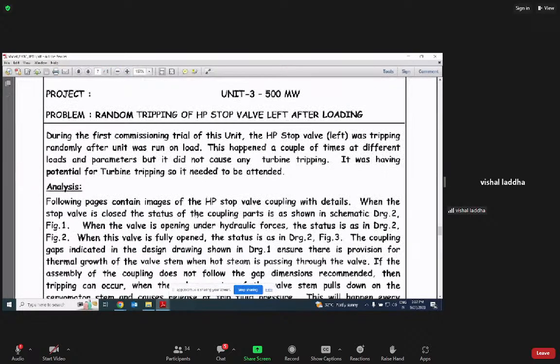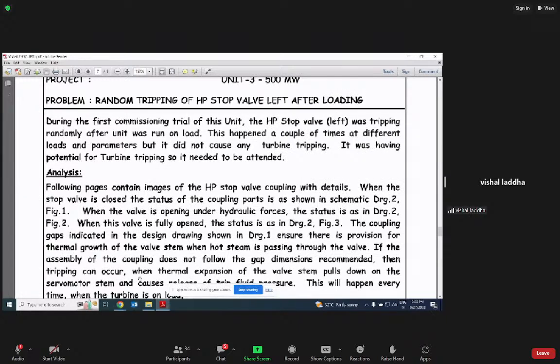Next is case number 2: random tripping of the HP stop valve left after loading. This is a 500 megawatt case study. During the first commissioning trial of the unit, the HP stop valve left side was tripping randomly after the unit was run on load. This happened a couple of times at different loads and parameters.